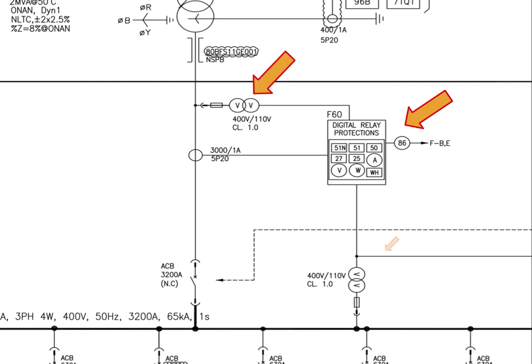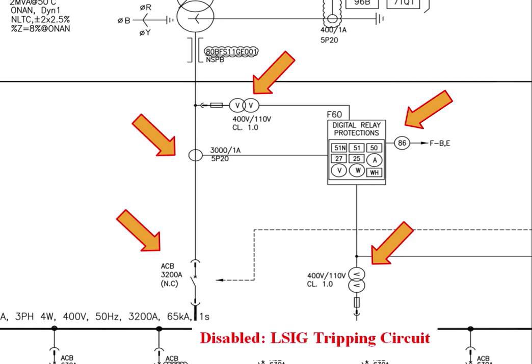Okay, right now we have two voltage transformers. One is connected on the secondary side of the transformer or on the incomer, and the other VT is connected on the bus of the LV switchgear. We also have a current transformer which is connected on the incomer side of our LV switchgear. Here we have an air circuit breaker. But for this topic, since we are having a relay, we are going to disable the LSIG tripping circuit of our air circuit breaker.